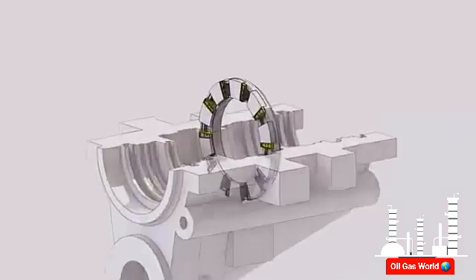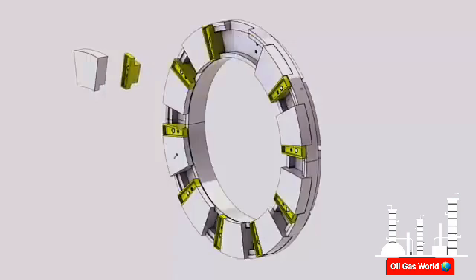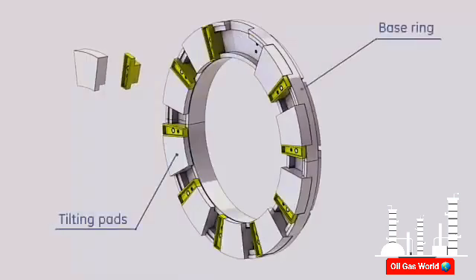The inactive thrust bearing is a tilting pad non-equalizing type bearing. A non-equalizing type bearing is also capable of sustaining high axial loads, but less tolerant of shaft and housing misalignment. This bearing is functionally identical to the active thrust bearing, except that it doesn't have leveling plates. Instead, the tilting pads are directly supported at their back by the base ring.